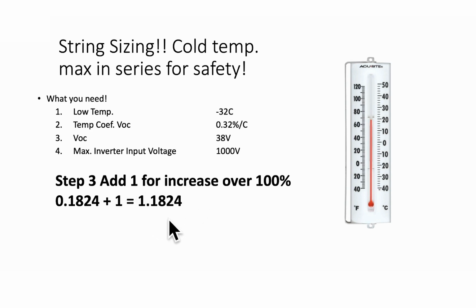You also can see in the National Electrical Code, there's a table, 690.7(A), that has all these temperature correction factors for different degrees, and it's just a different method than using the coefficients, but we usually use the coefficients because we are coefficient, or at least efficient.